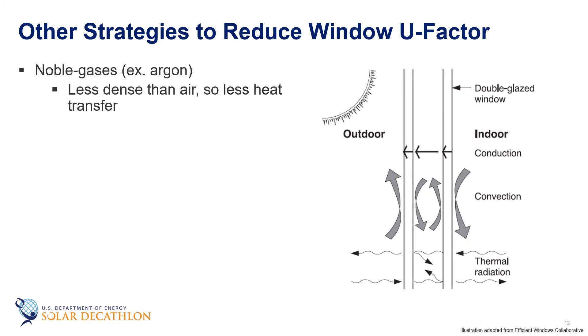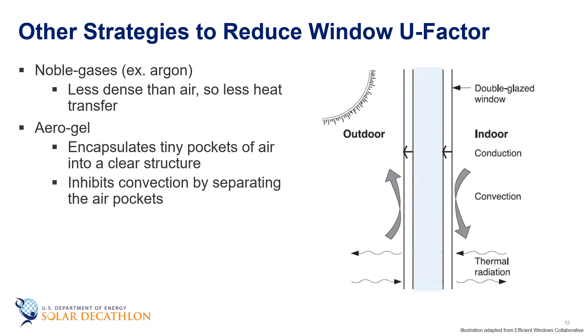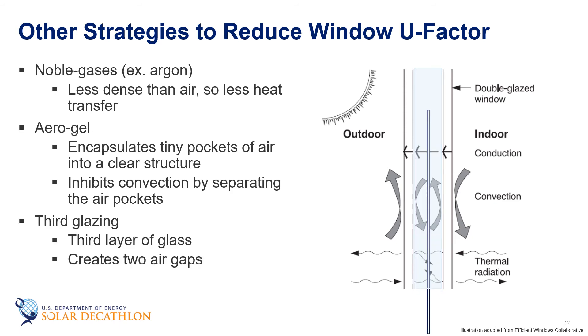In addition to tuning the gap to minimize convection, different gases can fill the gap to further increase thermal resistance. Using noble gases such as argon instead of air minimizes heat transfer because they are less dense and have fewer molecules to move heat from one pane to the other. A product called aerogel encapsulates tiny bits of air into a clear structure, inhibiting convection by placing air into separate pockets. Another strategy is to add a very thin piece of glass between the first two layers, creating three panes and two air gaps to further decrease the overall U-factor.